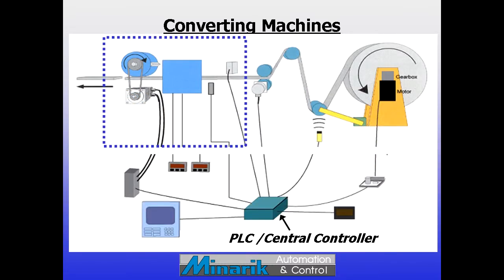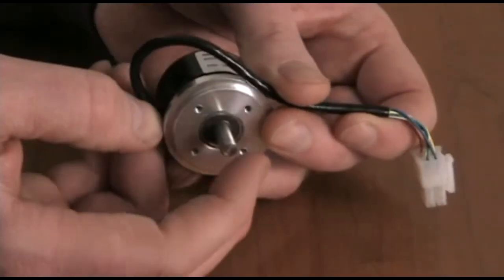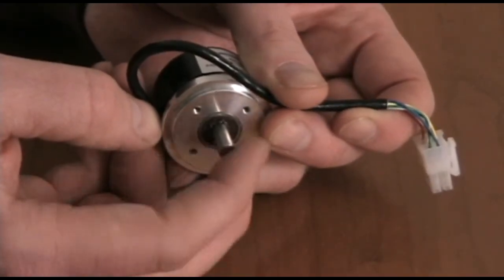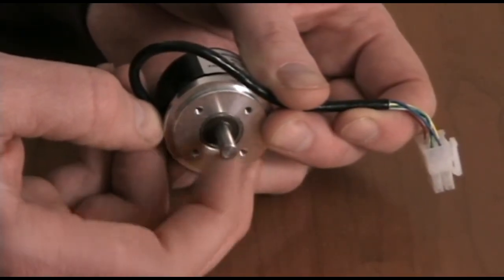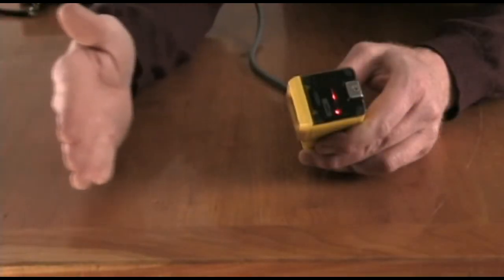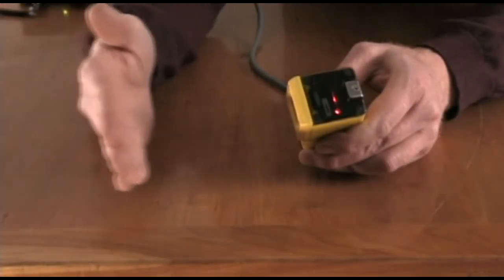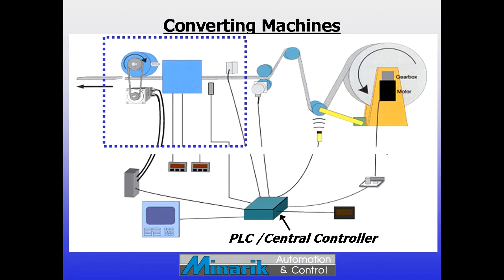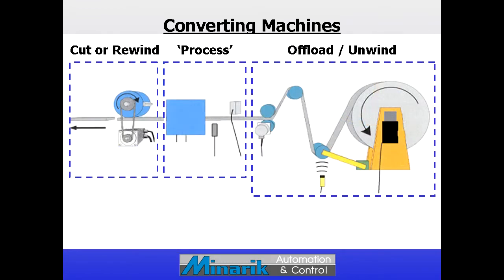To do this, a master controller or PLC knows the amount of material that will be needed downstream. It can also take information from encoders that ride directly on the material roll, or analog sensors that put out a variable voltage as web tension changes. The controller can then send speed commands to an AC or DC motor drive to speed up or slow down the offload. The result is a constant material speed that matches the need of the processes downstream.